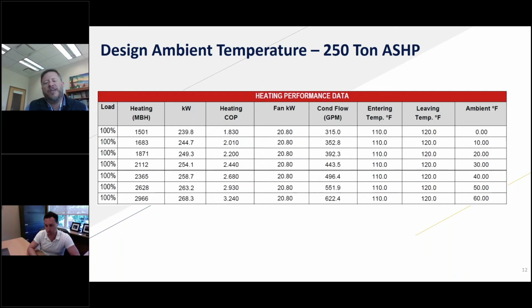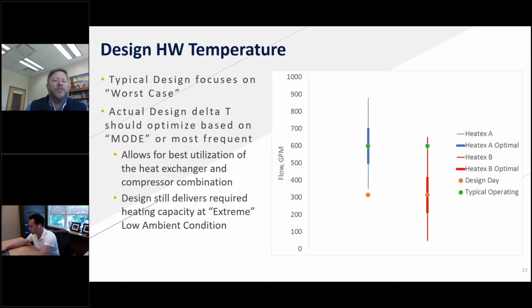And so now if we start looking at how we design our system, how we design heat exchangers, especially if we're going to be in a variable flow environment, it starts to be something that we need to look at. One of the things that we do a lot of talking about is, okay, now I'm going to go to my heating design day. The ASHRAE design point for New York is 13 degrees. But what we're seeing more and more of is, we're all trying to be responsible, and it's great that we say it's 13, although we all know that it's gotten colder than 13. And if you look at the 20-year extreme or the 100-year extreme, it's going to show something that's less than 13.